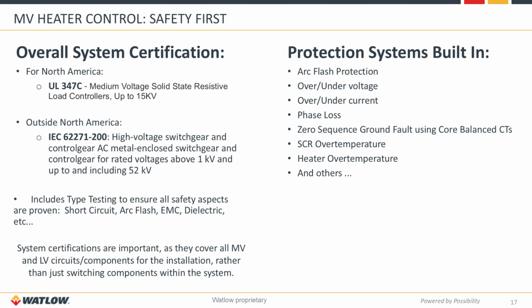They do include type testing to ensure all of the particular aspects for safety have gone through a third-party witnessed inspection to ensure adequate operation of the unit. Whether that's short circuit, arc flash, EMC, dielectric, heat rise type testing, all of this has been completed for both the North American units and the IEC units throughout the globe. So again, a total overall certification of the system to ensure that the third-party safety aspects have been taken care of.